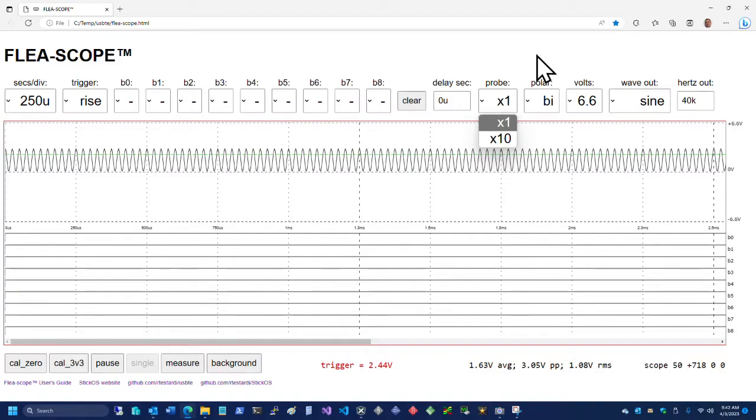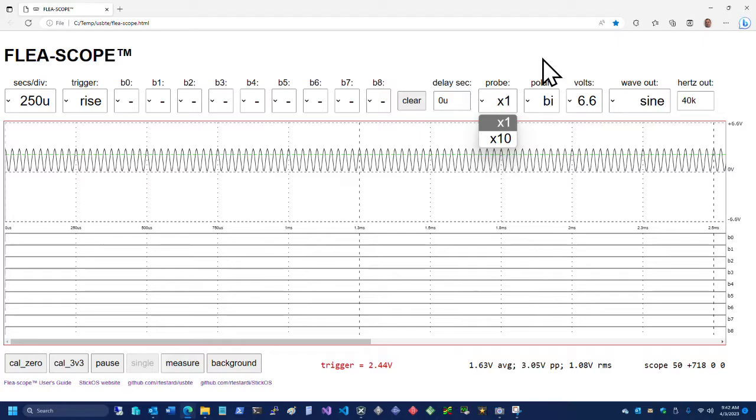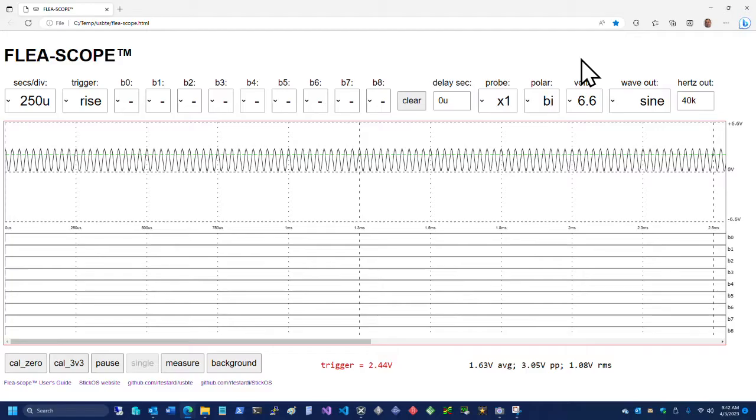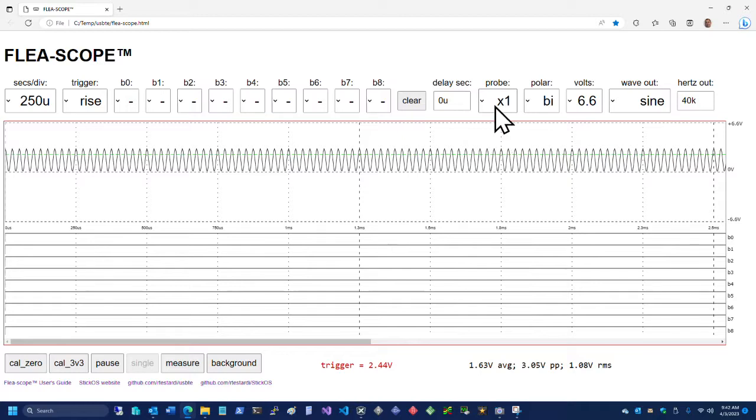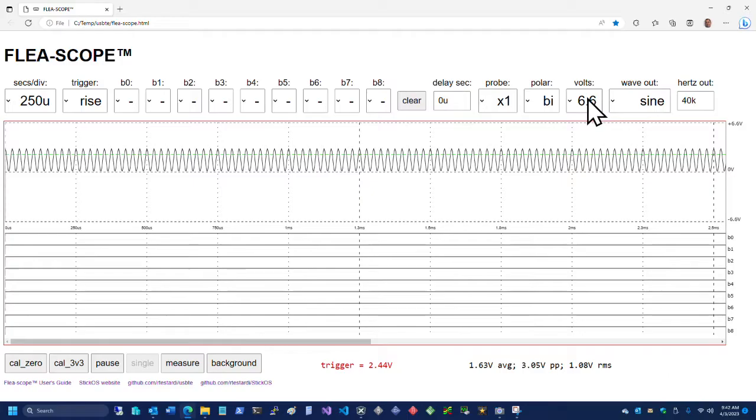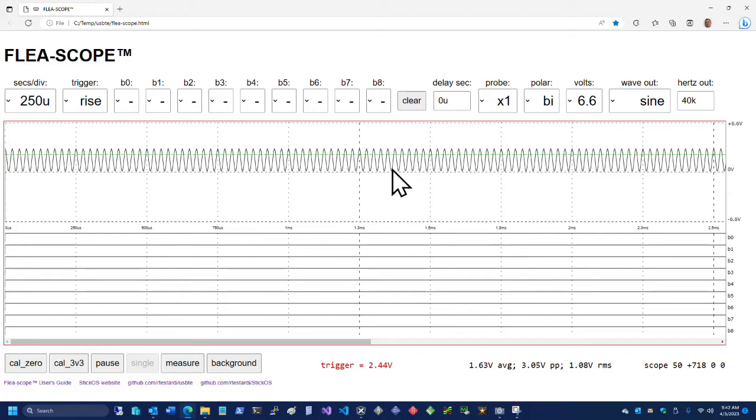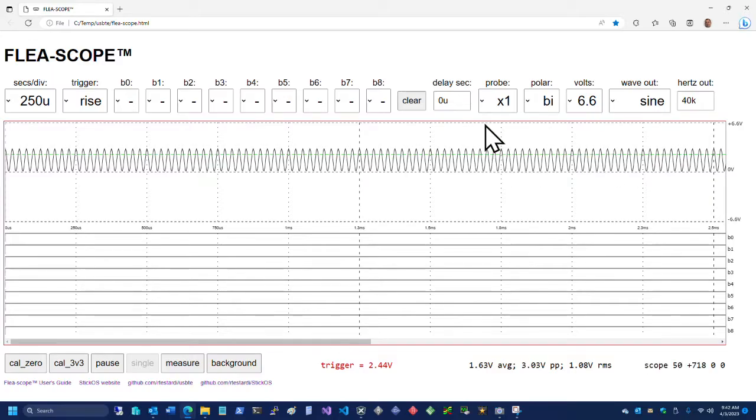Times 10 probe requires a slightly different calibration. And we haven't gone through the calibration step here. But basically, calibration takes five seconds. But we have not actually done it. And it will tell you if it hasn't done it yet. And if I were to switch to the times 10 probe, it would make us go through the calibration step. Anyway, so basically, we can zoom in and out on the voltage, we can zoom left to right on the time. And that's basically a brief introduction of the analog FleaScope. I'll be right back with the introduction to the digital.